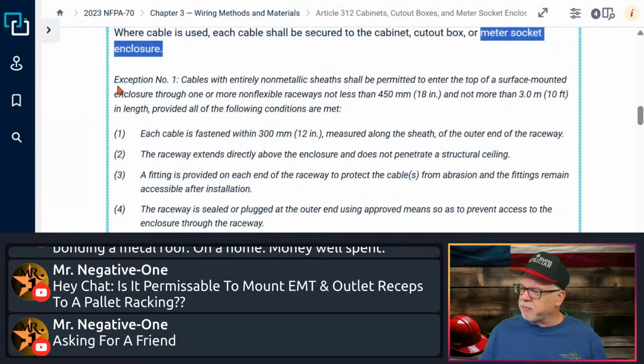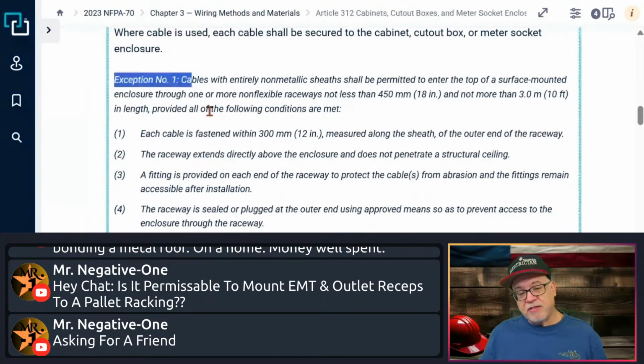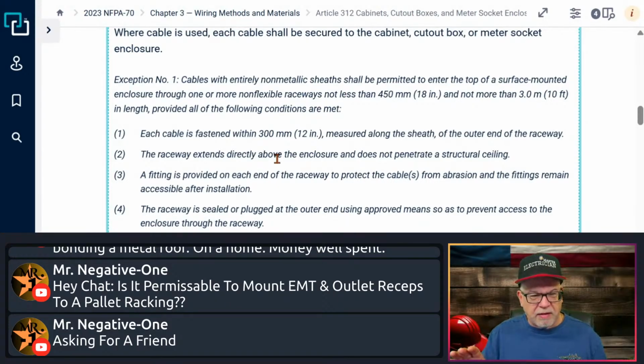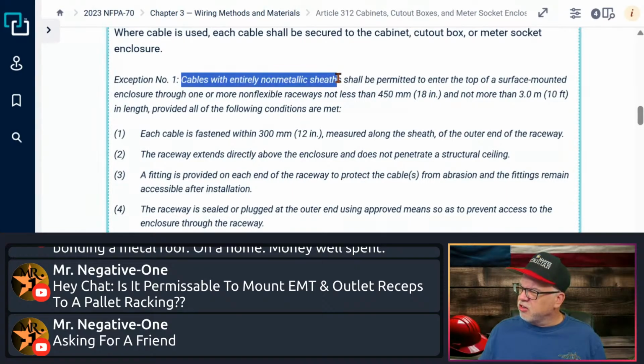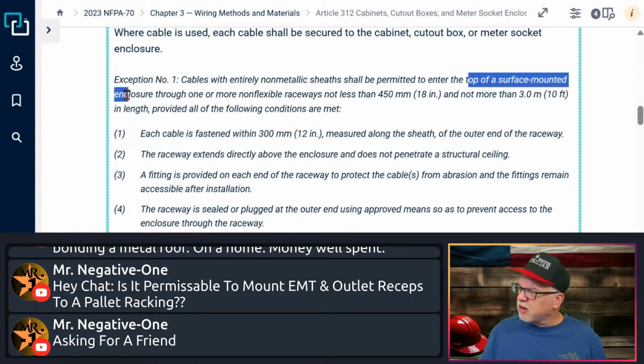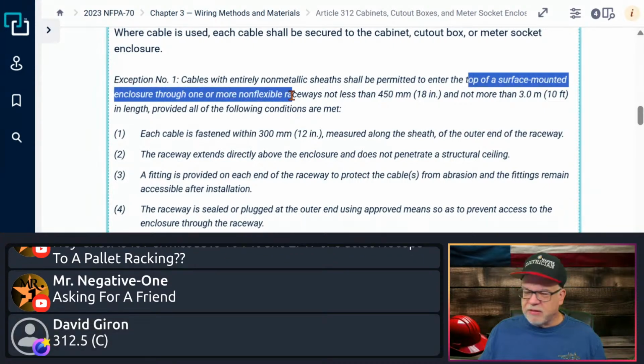There is one exception to this rule. And to meet this exception, you have to follow all of these rules. Not one of them, not a couple of them. You got to meet all these rules. Okay? So cables with entirely non-metallic sheathing shall be permitted, okay? Permissive rule, so permissive, to enter the top of a surface-mounted enclosure through one or more of the non-flexible raceways. Top, not back, top, okay?